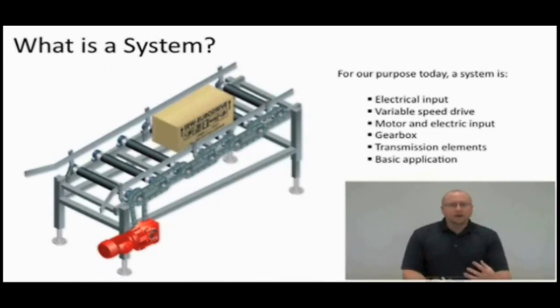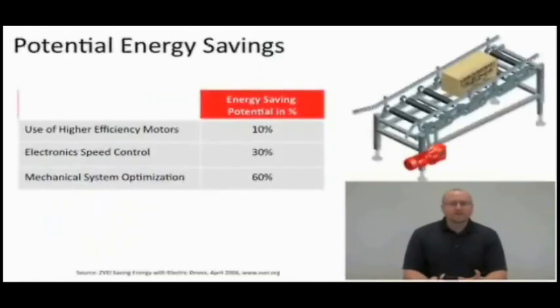The input power, a variable frequency drive or an automatic speed drive, they all go by different names. I'll be referring to them as a VFD, or a variable frequency drive here. The output of the VFD goes to the motor, the motor turns the gearbox, which can turn a transmission element like a chain or a belt, or be directly coupled to the application, which could be a conveyor or a hoist or anything like that. That's an entire system, and we're going to break a system down into its individual components, see where we're losing power and how we could possibly affect that. But before we do that, I just want to give a brief overview of where we can save energy, where we have the most potential to save energy.